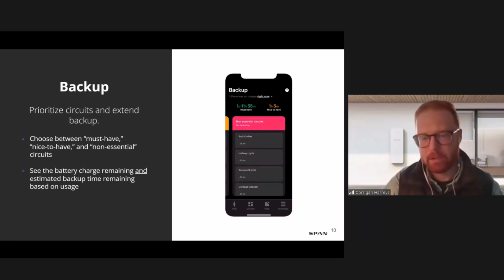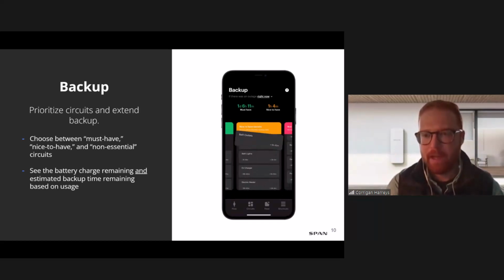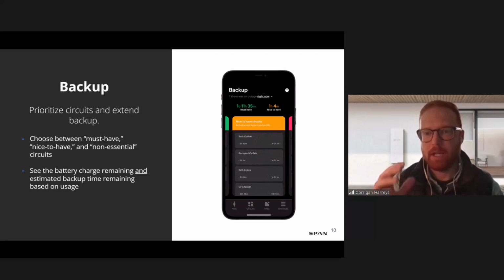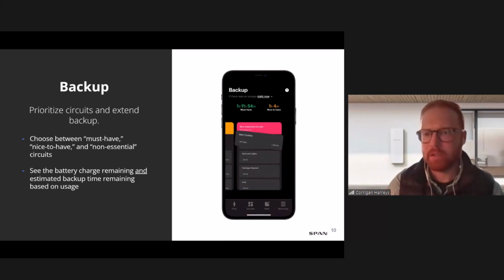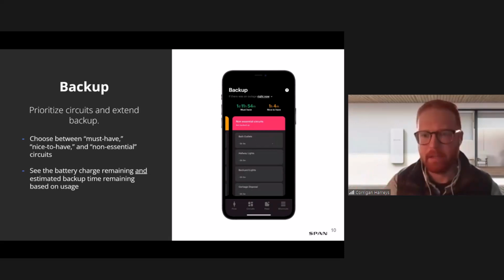SPAN also does automatic load shedding. We'll always shed the non-essential circuits for you, and at 50% battery life, we'll shed the nice-to-have circuits. During installation, if there are circuits you never want shed, your installer can tag them as non-sheddable, just as others can be tagged sheddable, giving you an extra level of control.